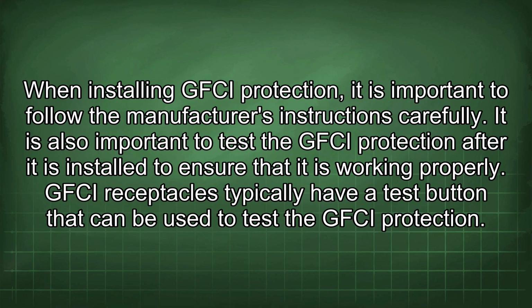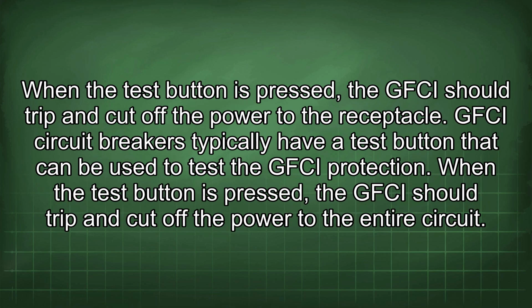When installing GFCI protection, it is important to follow the manufacturer's instructions carefully. It is also important to test the GFCI protection after it is installed to ensure that it is working properly. GFCI receptacles typically have a test button that can be used to test the GFCI protection. When the test button is pressed, the GFCI should trip and cut off the power to the receptacle.